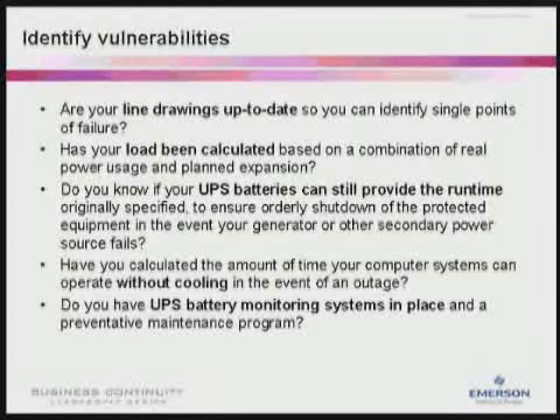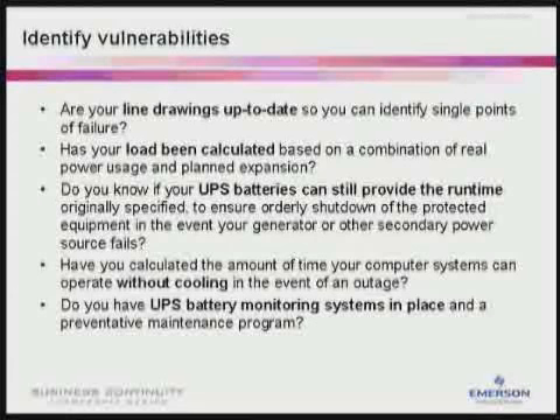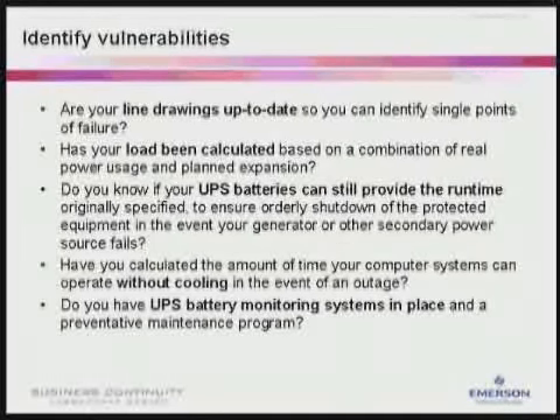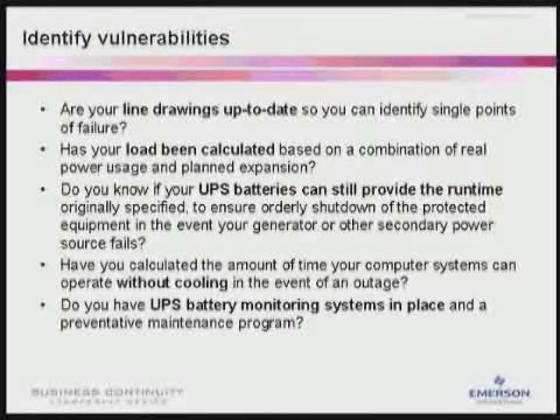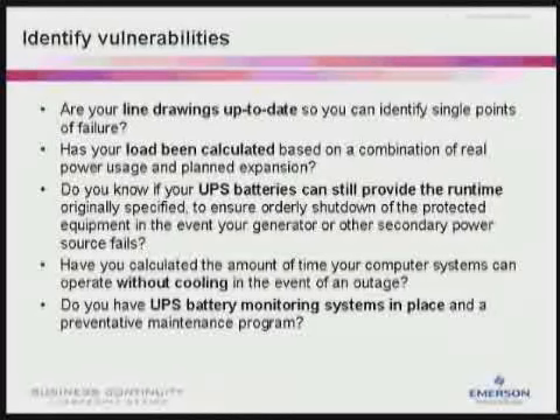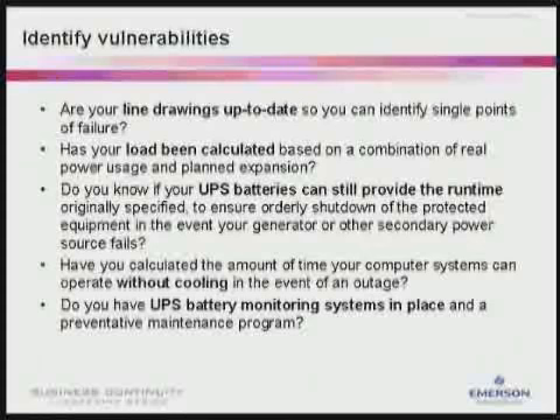These are just some of the questions you should ask yourself as you begin to prioritize steps to improve your resilience. Are your line drawings up to date? Has your load been calculated based on real power usage? Do you know if your UPS batteries can still provide the runtime you need? Have you calculated the amount of time your computer systems can operate without cooling? Do you have UPS battery monitoring systems in place and a preventive maintenance program?